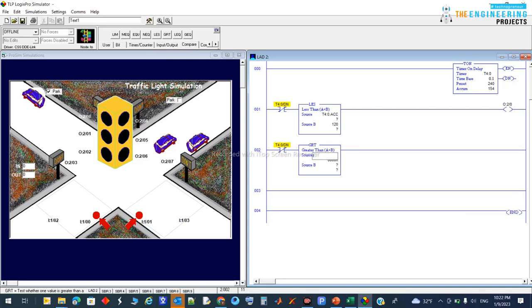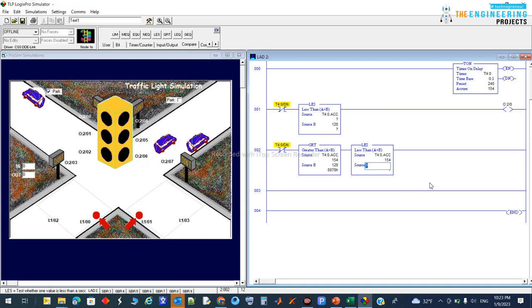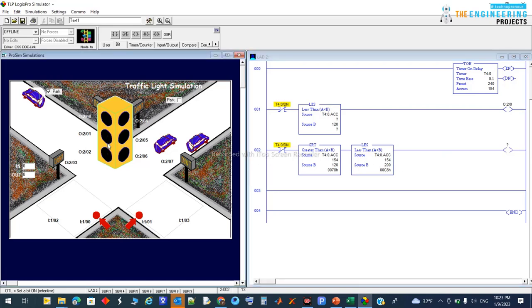For the green light rung: if T40's accumulator is greater than 120 but less than 200 — meaning greater than 12 seconds and less than 20 seconds, so an 8-second window — then I will run the green output. So after adding this comparison, I can run the green light.